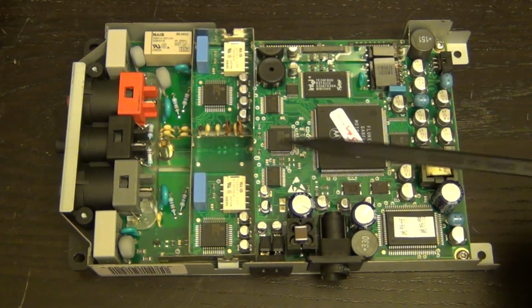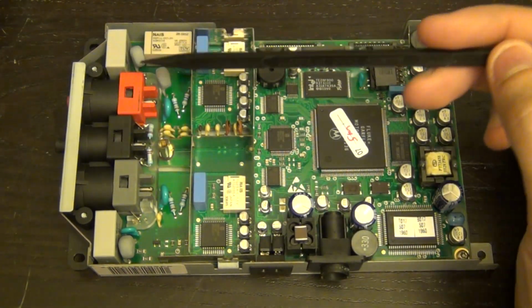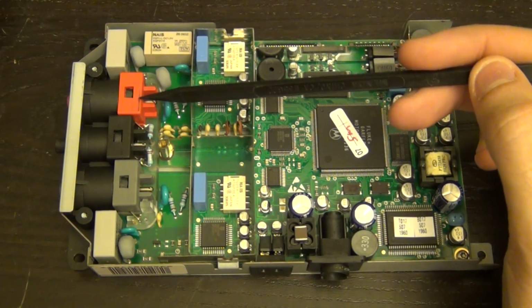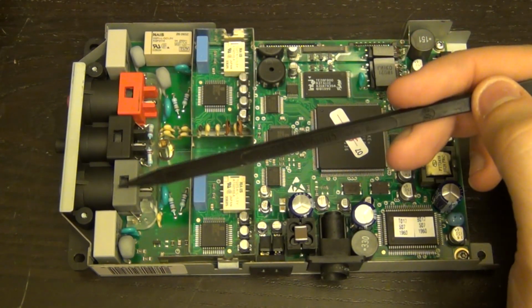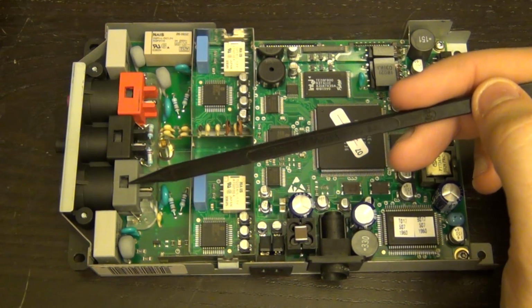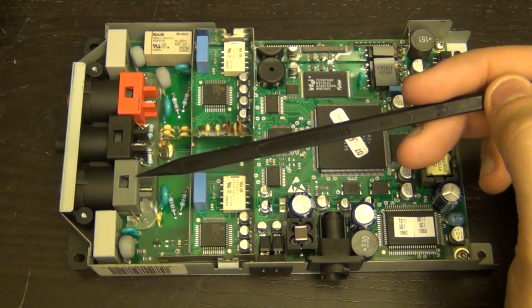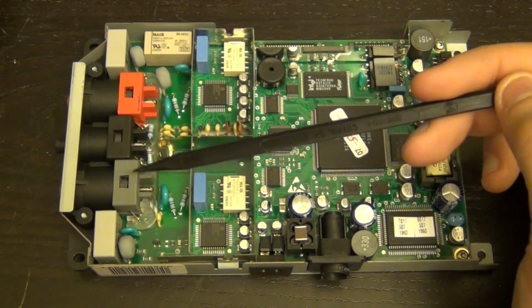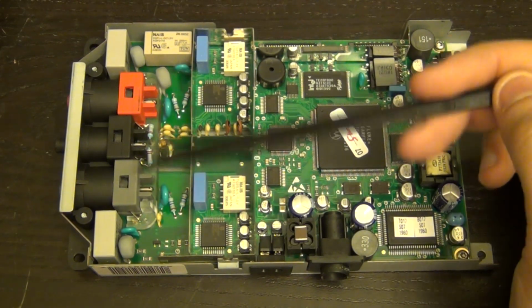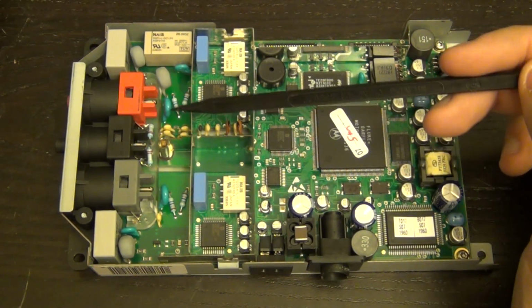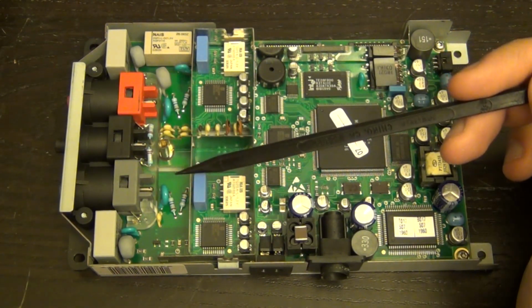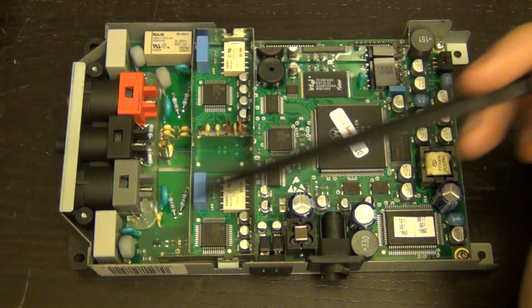You can see two separate input channels coming directly from the outside. The red one comes from the AC line, where you'd connect your voltage, and the black one is where you'd connect the loop for measuring current, and the clamp for measuring current—I'll show you that in a second. You can see the difference between these two pads and the input protection, a vast amount of it embedded in here.